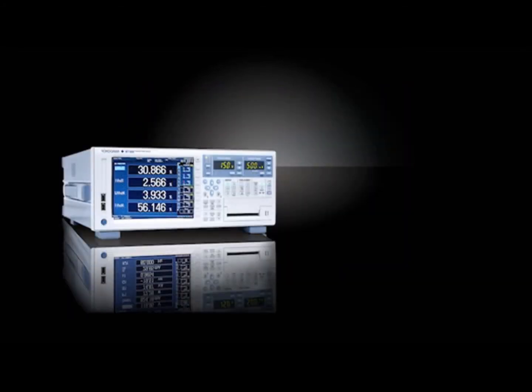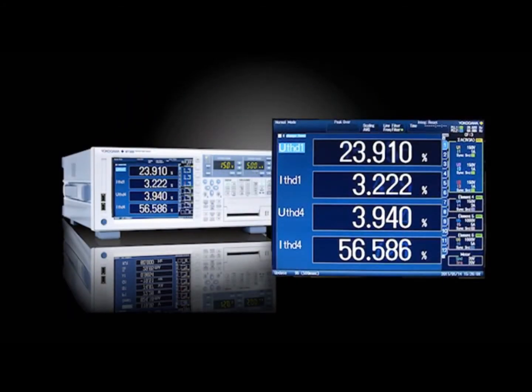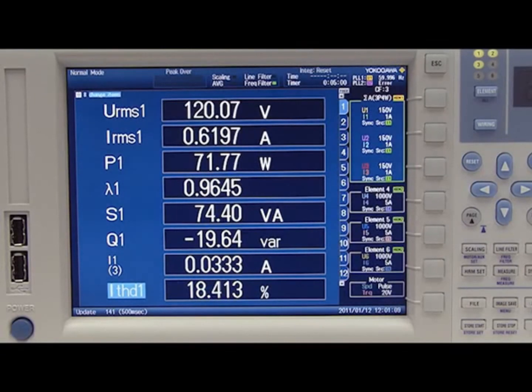The Yokogawa WT1800 offers an industry-first dual harmonic measurement function. This feature makes it possible to simultaneously measure the harmonic content and perform harmonic analysis on 2 different sources, such as the input and output of an inverter, variable speed motor drive, lighting ballast, uninterruptible power supply, or similar devices. In addition, the normal power parameters and harmonic data are measured simultaneously, providing for faster and more accurate power analysis.